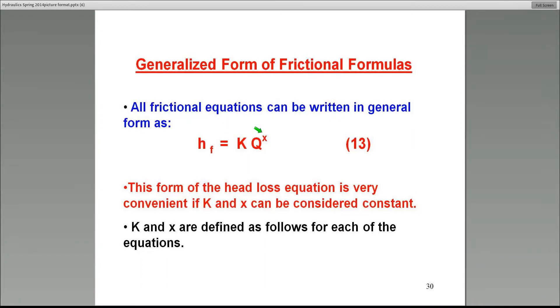One is the typical one that you're probably already familiar with, called the Darcy-Weisbach equation. For that, x is 2. And then the one that's most widely used in water systems is called Hazen-Williams. For that, x is 1.85. So in either case, all units must be consistent. For example, head loss due to friction will be in feet, Q in CFS.